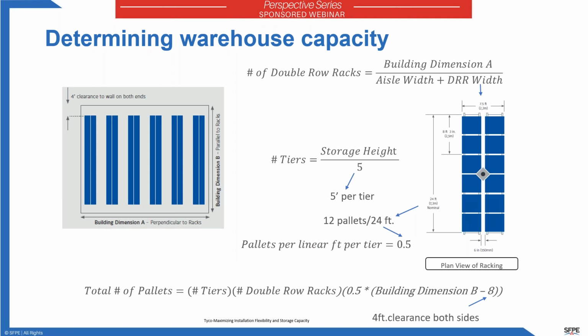So I came up with a set of equations for figuring out how much storage you could have in a warehouse. Now, since this is a webinar sponsored by the Society of Fire Protection Engineers, I'm going to make the bold assumption that there are lots of engineers on the call, and the higher mathematics of multiplication and division is not an issue with you guys. So at the end of the day, my warehouse capacity example is based on the total number of pallets that can be stored. And so basically the total number of pallets is based on how many double row racks can fit into a space. So here on the left, you see double row racks. So I need to calculate how many of these I can fit given my dimension A.